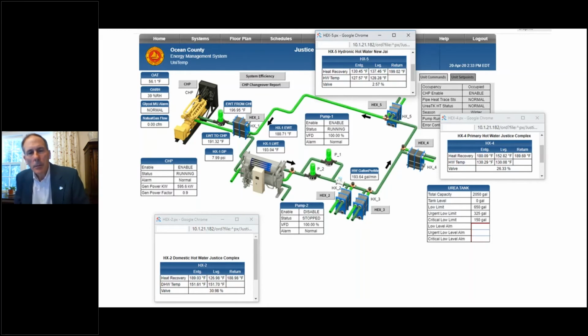All of the data being collected for the system is being collected in the building automation system for the facility. This is a graphical representation of the system. You can see in the upper left-hand corner is the combined heat and power unit, circulating glycol to heat exchanger number 1. Also being circulated to heat exchanger number 1 is the hot water that circulates through the building and is supplied to various thermal end users inside the building, such as the absorption chiller, various heat exchangers that provide thermal energy to the domestic hot water system and the building heating systems and the thermal reheat systems in the building.